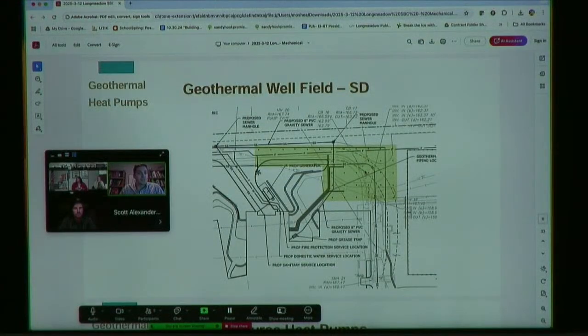It's a closed loop borehole with a supply and return HDPE pipe that's inserted into the borehole and then filled with a thermally conductive grout, which basically seals off the groundwater from the surface water. This is just showing a preliminary layout of where those boreholes would be located. They are piped together in a reverse return configuration, which just means that we're equalizing flow through the individual boreholes.